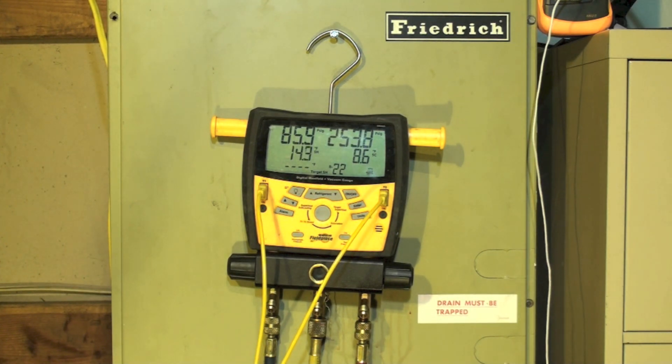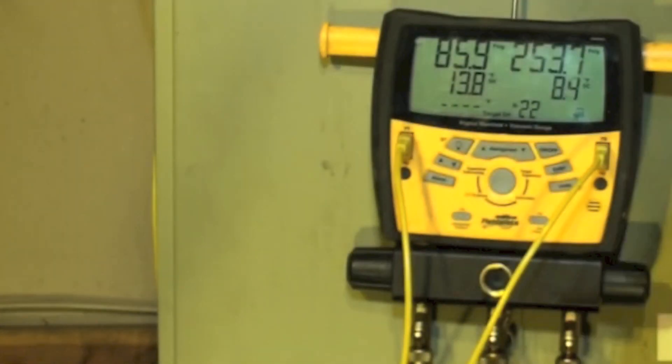Okay, 14 point... oh my goodness, that came really close. I'm going to have to redo the target superheat, but I think it was about 15. That was actually closer than I thought. I thought it would be a little more off.